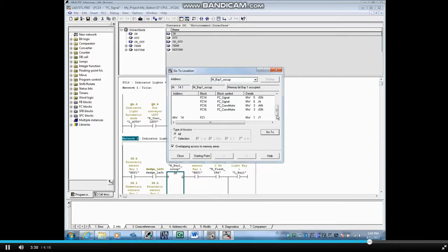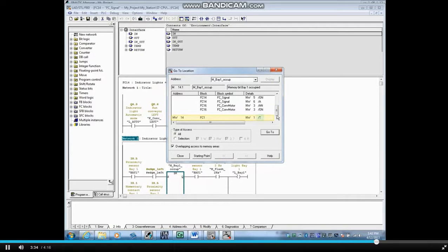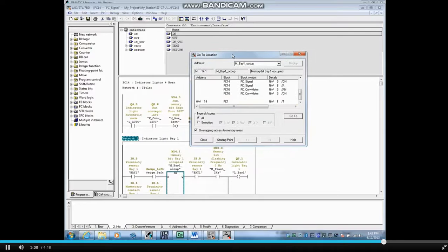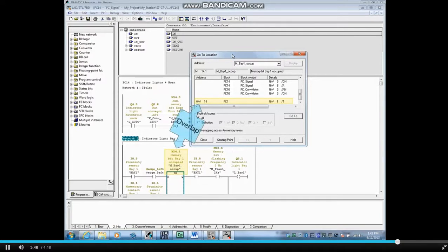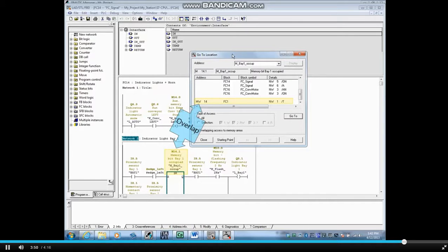You can see that memory word 14 is in use. The T means that data is being transferred or written to this address. Since memory 14.1 is contained in memory word 14, there would be a conflict because two different pieces of code are attempting to write to the same location, both involving M14.1.